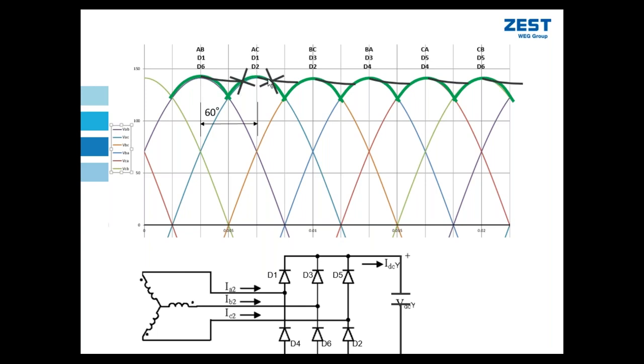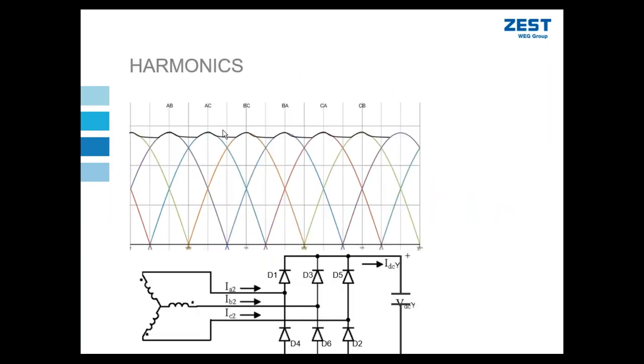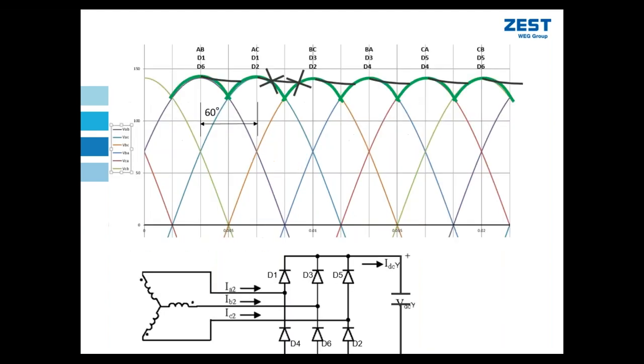When our phase-to-phase voltage, which is between those two crosses, is higher than my capacitor voltage, then my supply is providing the energy. However, when I move to this interval, my capacitor voltage is higher than my phase-to-phase voltage. During this period of time, the energy required from my load, which could be a motor on the output of my VSD or whatever, is no longer drawn from the supply. The supply voltage is lower than the capacitor voltage. Energy is drawn from the capacitor in that interval. Just to demonstrate, okay, so sorry, let me just go back here.